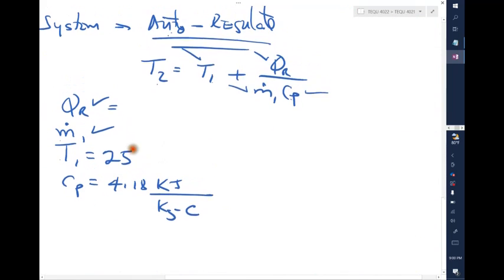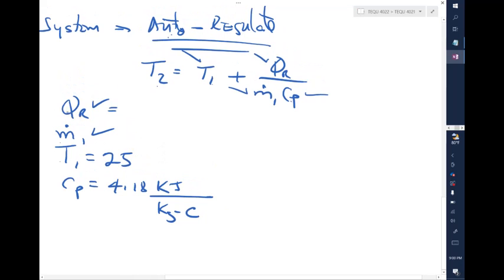For example, let's say that QR is adjusted to 50%, so the maximum is 5 times 50% divided by 100, which is 2.5 kilowatts. All right, what about the M1, the flow of material? That flow will be the maximum, which is 0.126, multiplied by the adjustment.